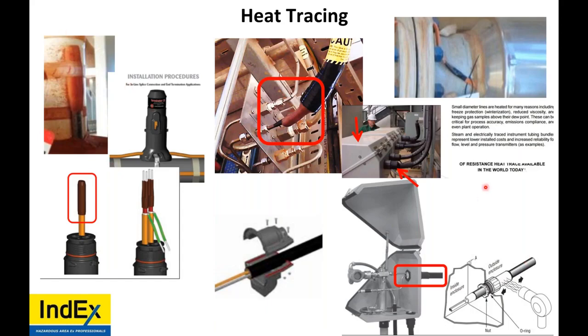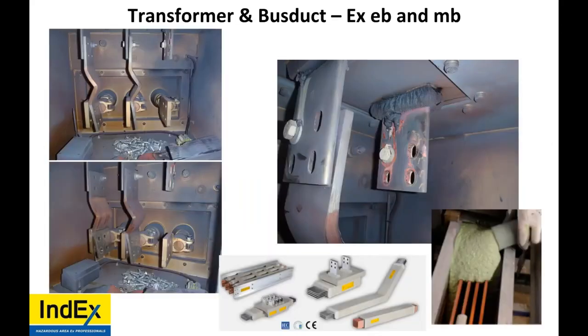That's what he says. But right here, this is heat trace that was terminated together or repaired with cable tape. Super 33, 3M Super 33. So that's going to melt, possibly catch on fire. Remember what I told you about the transformer? This is the other side of it. So what happened? Well, there were torque marks on the bolts, but then somebody took the bolts off, and this thing ran for a few months.